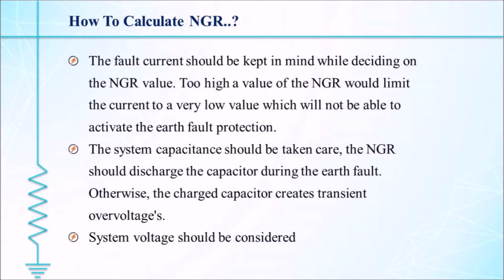Here I am giving you an idea about the dominating key element, that is how to calculate NGR. There are some considerations while deciding the value of NGR. They are as follows. First, it is a must that the fault current should be kept in mind while deciding the NGR value. If the value of resistance is too high, then it will limit the current to a very low value, which will not be able to activate the earth fault protection like relays of the system to be protected.